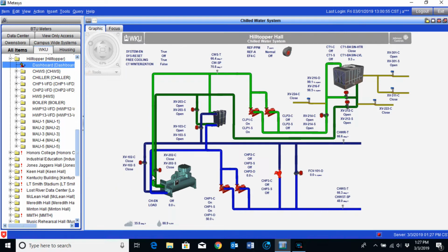Of course, these valves here will then close, and these valves here will then open. You can see the blue lines representing the chilled water lines, and the green lines representing the condenser water lines. Up here in the upper right, we have the cooling tower itself, and what we will do is flow the water through the heat exchanger.